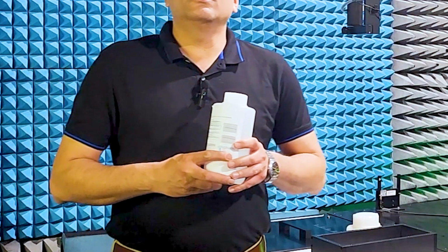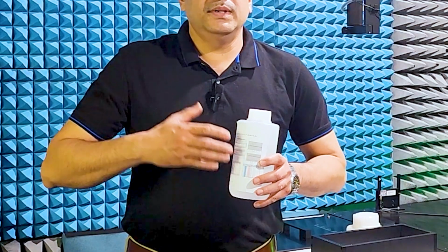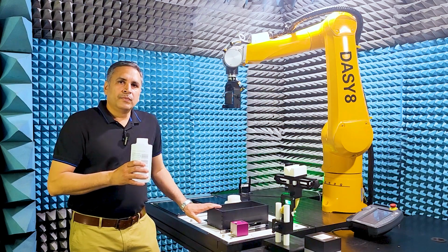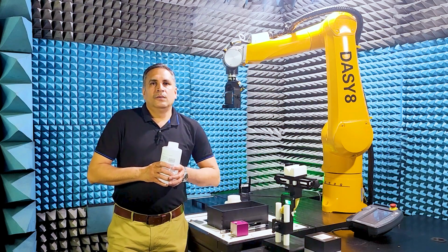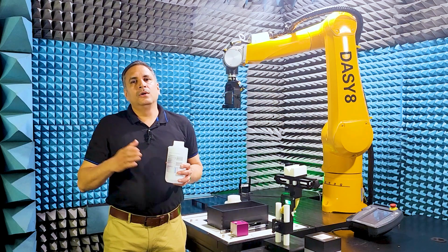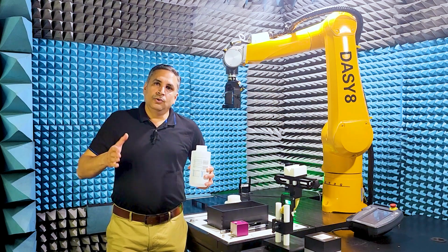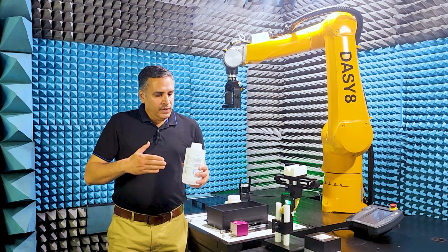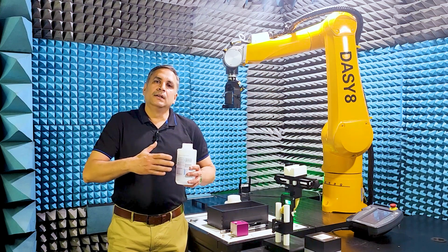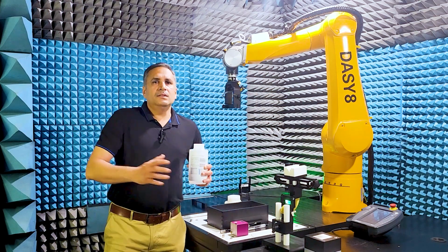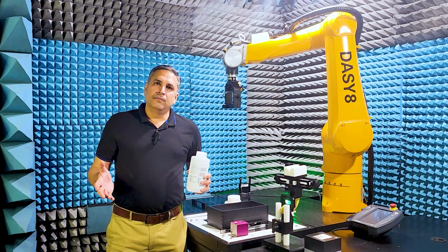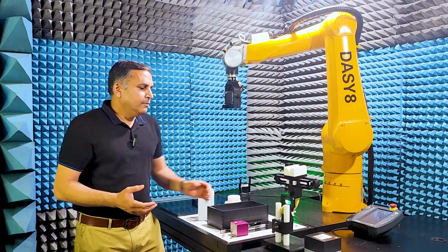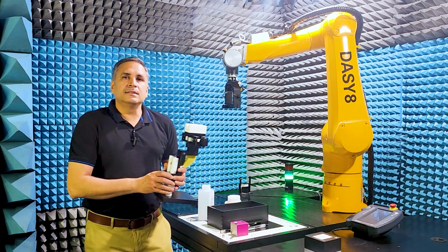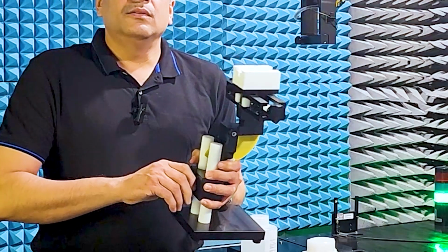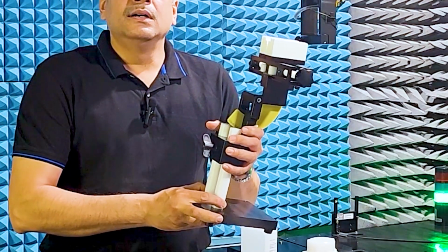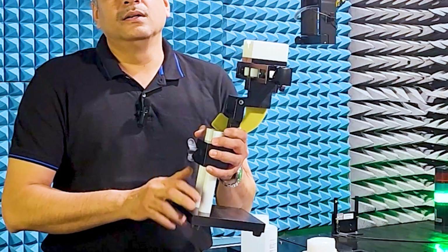The skin simulation liquid SSL30 has been designed together with the phantom. It is valid for the same frequency range from 24 to 30 GHz and has low loss. In other words, much larger penetration depth, but combined with the phantom, the same absorbed power density as skin. Finally, I have the phone mounting device MD4 APD version 5 to position the handheld transmitters precisely below the phantom.